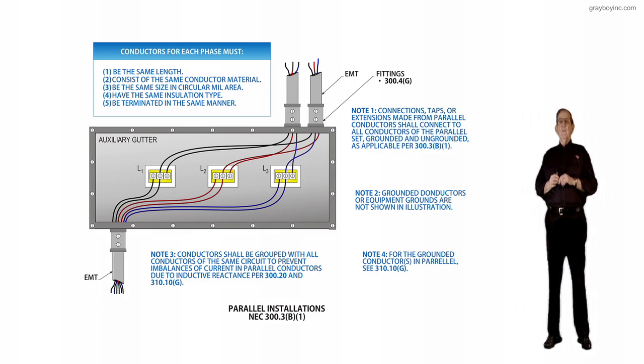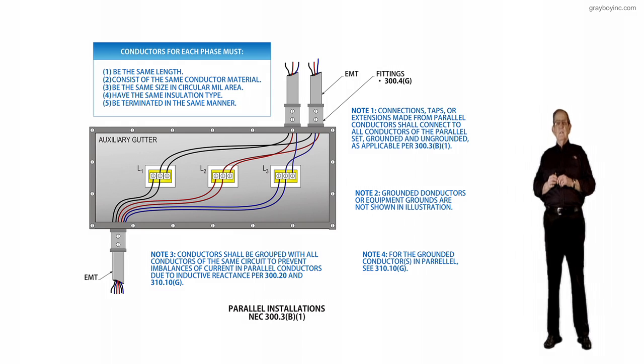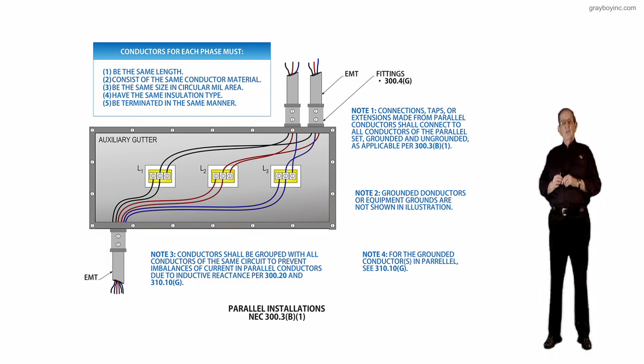Review the notes and 300.3B1 very carefully when you parallel conductors. Also look at 310.10G and for equipment grounds, review 250.122F. With these guidelines, we won't be making these errors when we connect conductors in parallel.